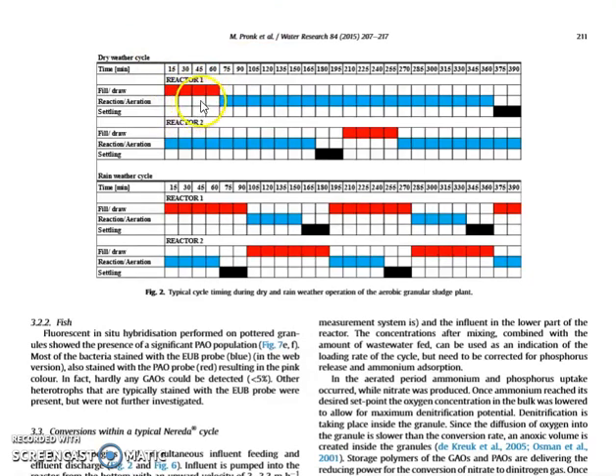Since there are two reactors, they should always be out of phase. When one is filling up, the other is in operation. When one is running the biological steps, the other is in fill and draw — where you draw off the excess water first and then fill. Then you start over again with the anaerobic, aerobic, and anoxic periods.